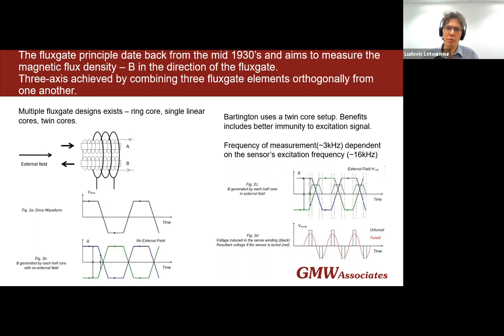So that induced voltage could be measured directly, but in most cases, it is used to drive a feedback current into the pickup coil. And what we're measuring is the intensity of the feedback current through a scaling resistor, a precision resistor. And that gives us our voltage output of the field amplitude. Using that closed loop, that null mode, has a few benefits. It increases the linearity of the system and increases its sensitivity.